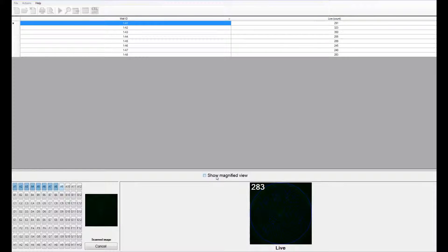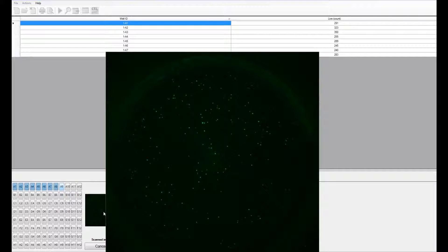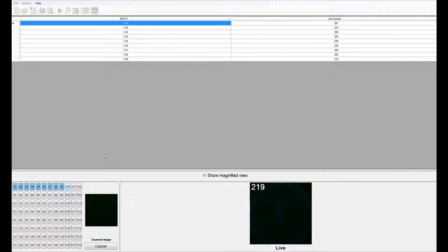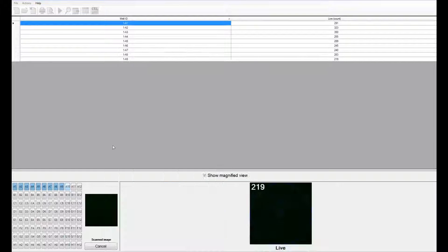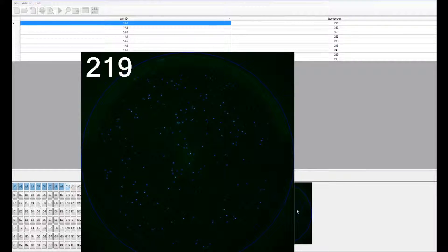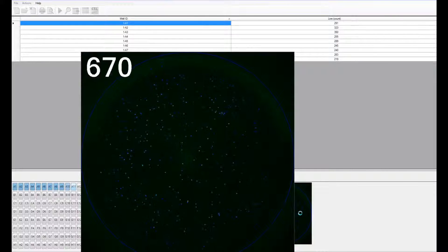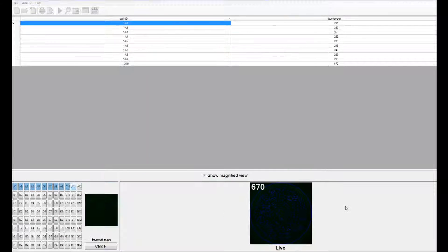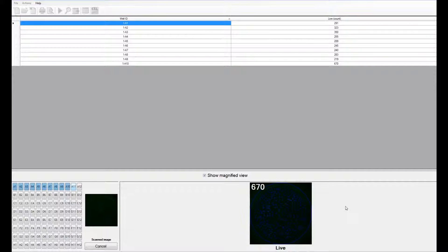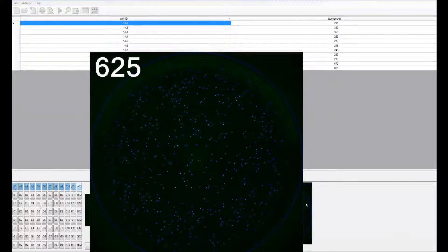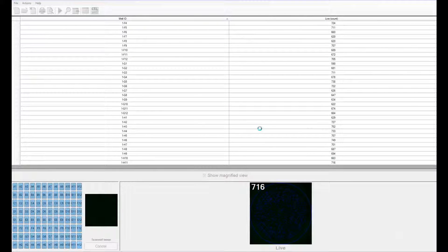By clicking on the show magnified view icon, you can either view a sample as it is being scanned, or you can view it after it has been counted. On your counted wells, you will see the cells circled with an overlay. These are representations of the cells that have been counted. Once all the chambers that you selected have been scanned and counted, you will be asked to remove the plate from the plate holder.